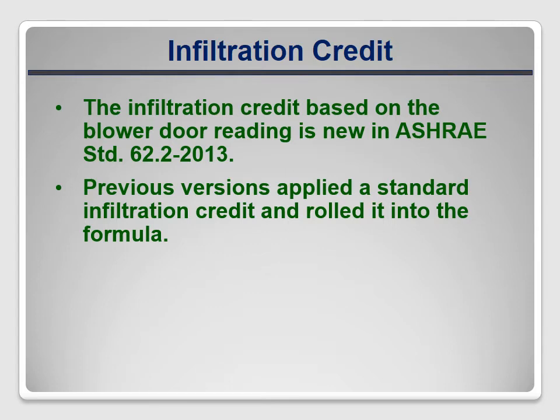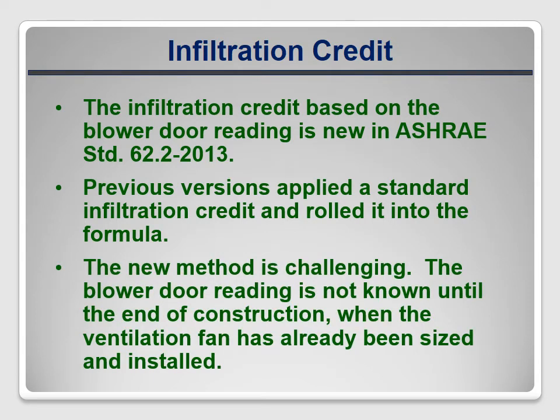This new method is challenging because the fan must be sized when the house is being designed, but the blower door reading isn't known until the house is completed. Raters working with builders often tell the builder to install a fan that meets the requirement without an infiltration credit rather than trying to guess at what it might be. The assumption is that the builder or homeowner can lower the speed of that fan based on the actual conditions in the finished house. The result may be a house that's over-ventilated with all of the associated issues.